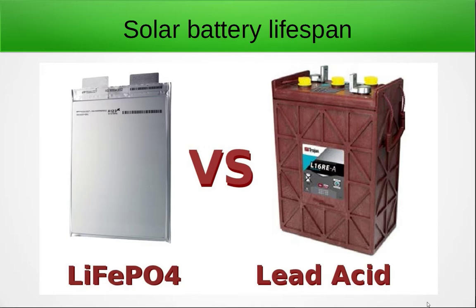Proper maintenance can also have a significant effect on your solar battery's lifespan. Solar batteries are significantly impacted by temperature, so protecting your battery from freezing or sweltering temperatures can increase its useful life. When a PV battery drops below 30 degrees Fahrenheit, it will require more voltage to reach maximum charge. When that same battery rises above the 90 degrees Fahrenheit threshold, it will become overheated and require a reduction in charge. To solve this problem, many leading battery manufacturers, like Tesla, provide temperature moderation as a feature. However, if the battery that you buy does not, you will need to consider other solutions like earth-sheltered enclosures. Quality maintenance efforts can definitely impact how long your solar battery will last.